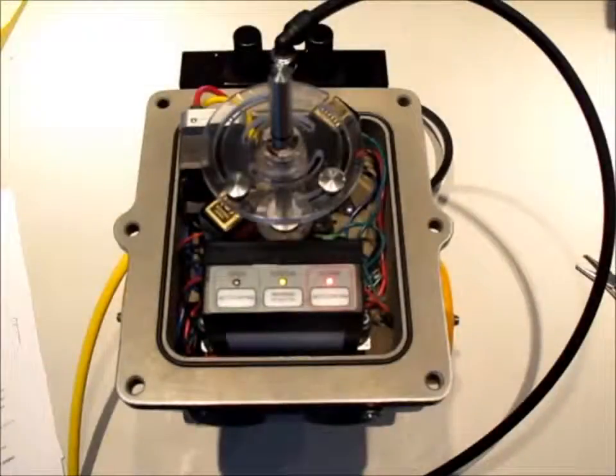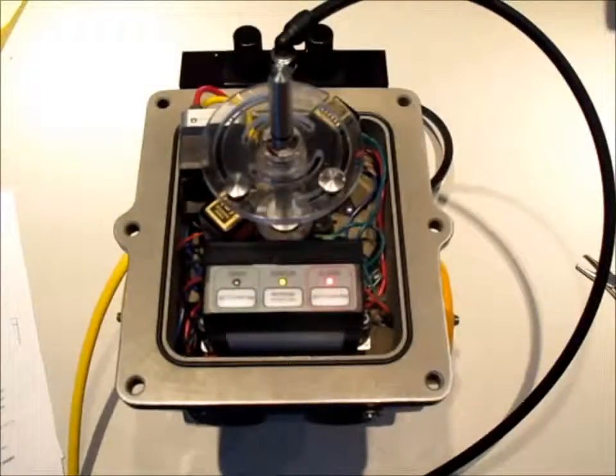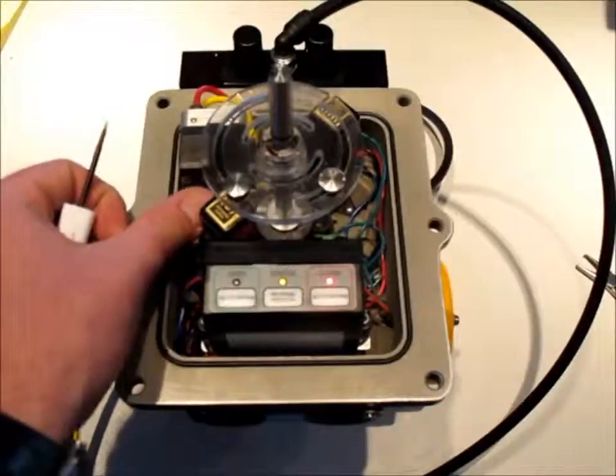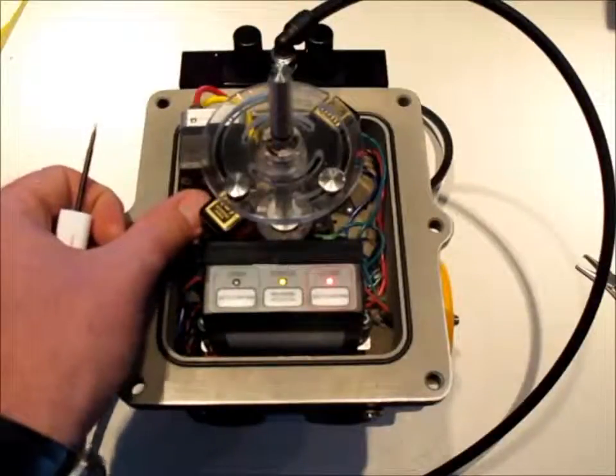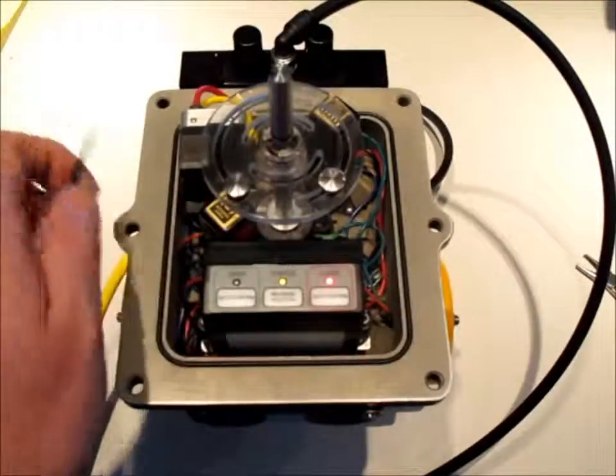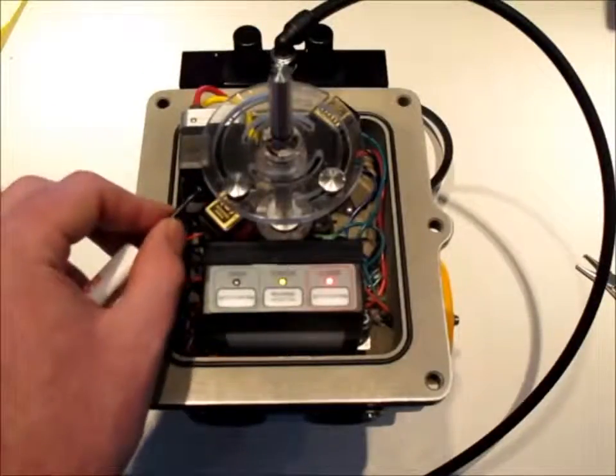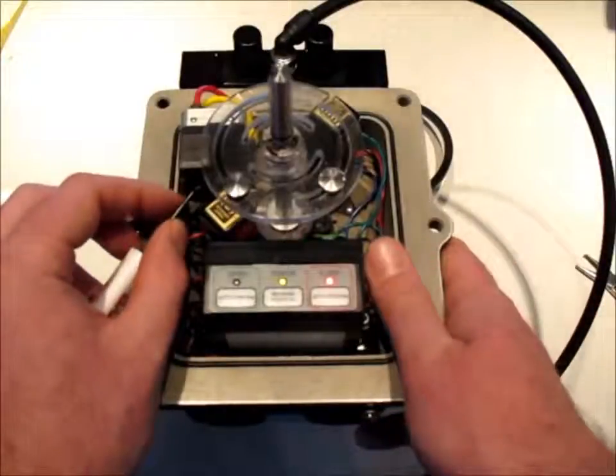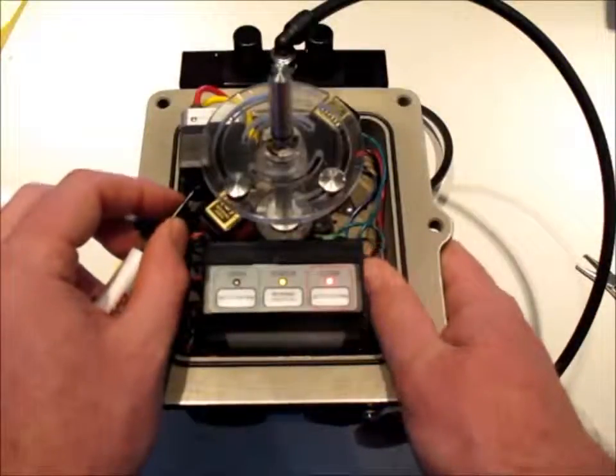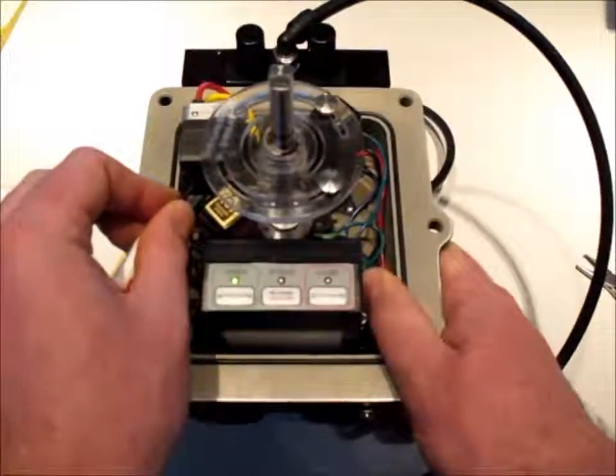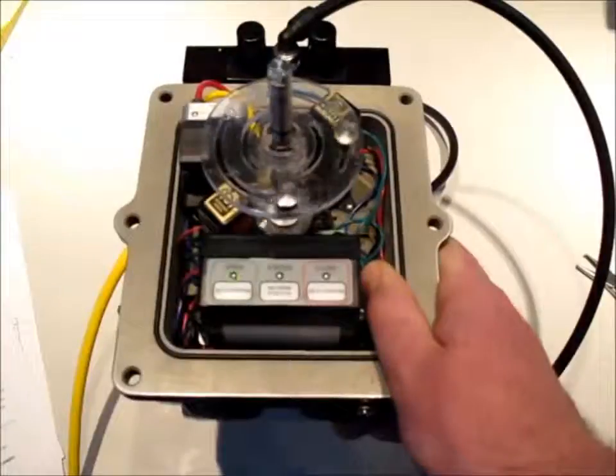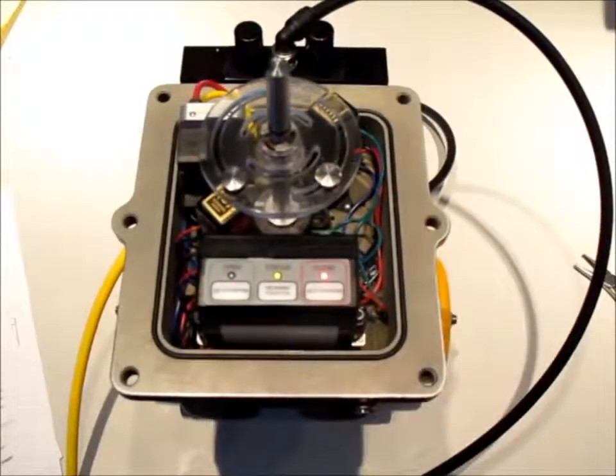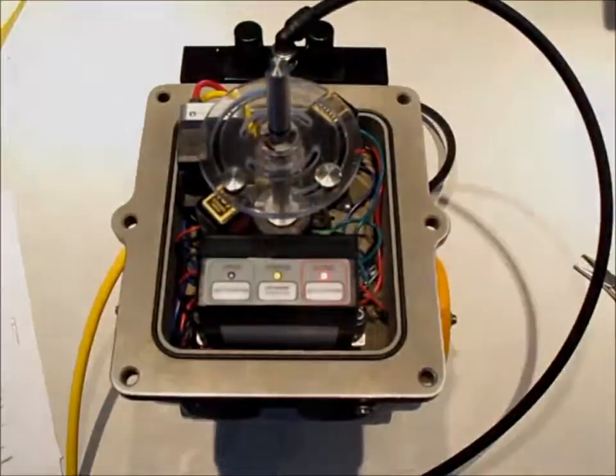You can manually override your integral solenoid by finding the small button on the back of the piezo. Using a screwdriver, press and hold this override. Once you release the override, you will return to normal status.